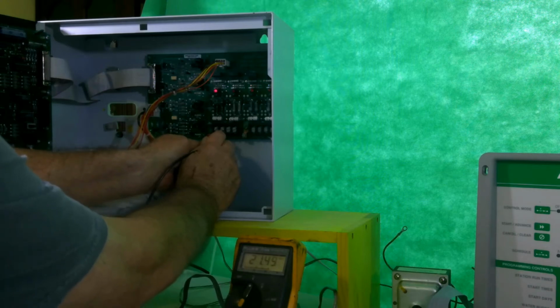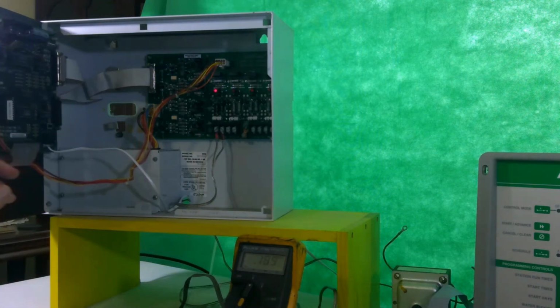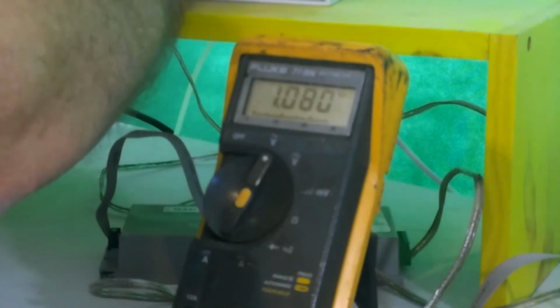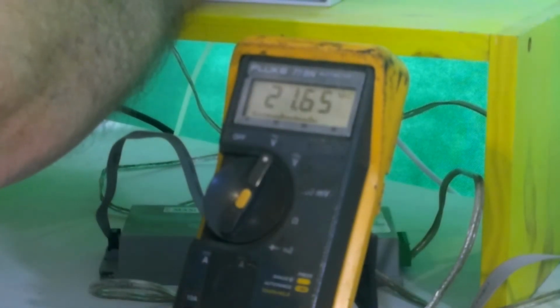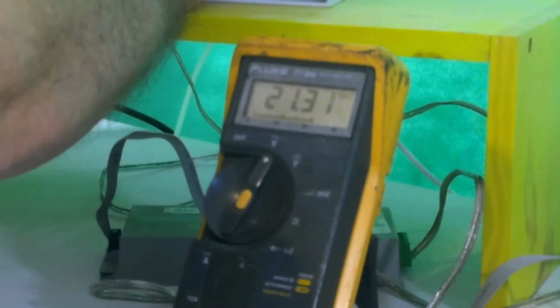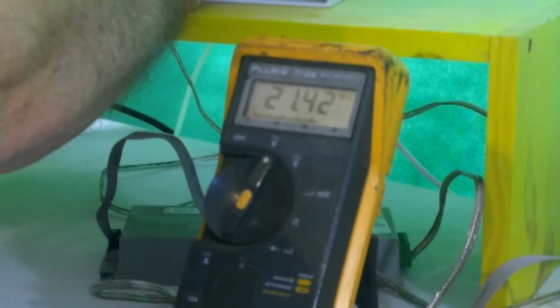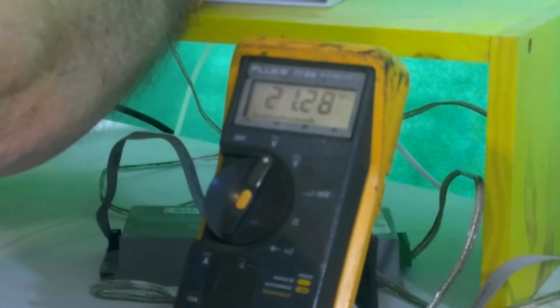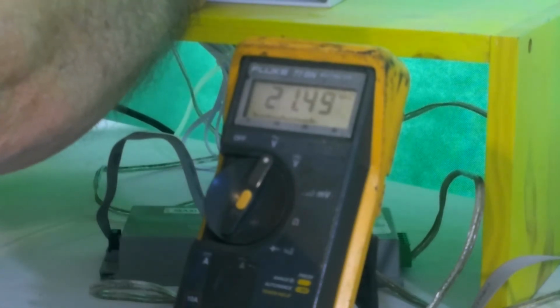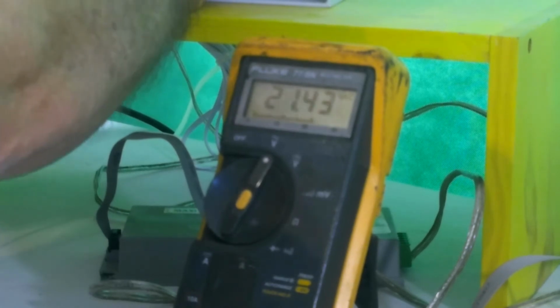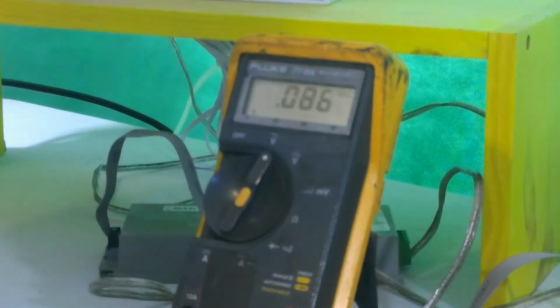So let me move up a little tighter, that way you can actually see the meter reading. As you'll notice, it drops down to 18, 19 volts when it's communicating, but when it's sitting waiting to check and go into field, it sits at 21 to 22 volts and it varies. You need to remember that number because that will be reflected in the two-wire module we're going to check in the field. If you're not getting that voltage, it says there is something wrong inside this MIM, most likely with the output board, which is this larger board in the back here.